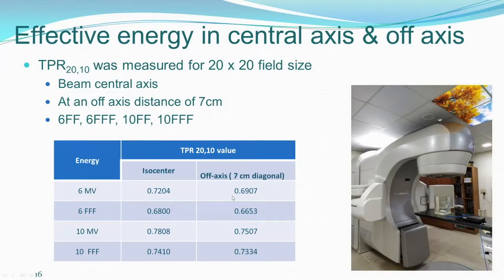So you see, there is a significant difference in the energy index. If you consider this as the energy index, it is 0.72 at the central axis and 0.69 at 7 cm from the central axis. But if you go to a 6FFF, the decrease is not that much, 0.68 to 0.66. Similarly, for 10 MV, it is 0.78 to 0.75. If it is 10FFF, it is 0.74 to 0.73. So the previous slide, which we looked at, where the energy is lower at the off-axis regions for the flattening filtered beam, is explained by TPR 20,10 here. I don't know whether this is the right method to do it, but it's interesting. It makes us understand much better.